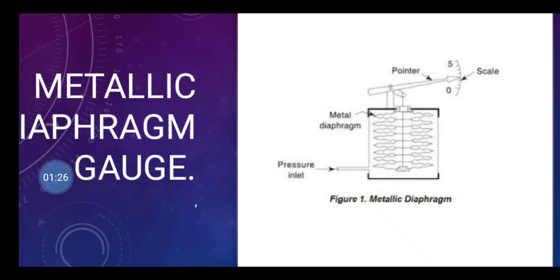The metallic diaphragm is flexible and made up of bronze. The pointer moves on a graduated scale which reads pressure. It is attached to the diaphragm. The force created by the pressure against the effective area of the diaphragm produces a deflection of the diaphragm. A spring helps to limit deflection. The motion of the diaphragm operates an indicating system or recording system.